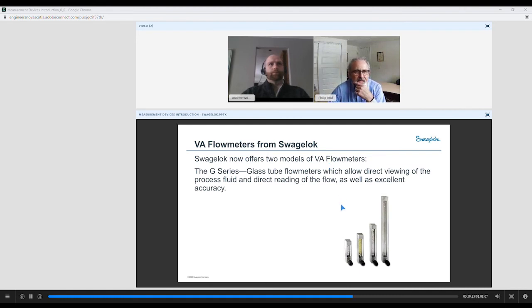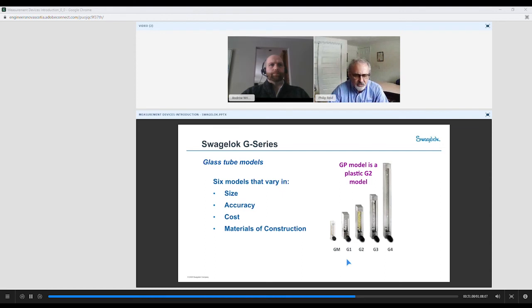So let's take a little look at these again. We offer sort of two models. We offer these in glass tube and some in plastic. There are some others, but they allow direct viewing, as we mentioned, from the front, and excellent accuracy ranges. The longer the tube, the higher the accuracy. The smaller the flow meter, the lower the accuracy. So again, very low, inexpensive setup costs here. On the glass tube models, there are 6. We also have a plastic model as well if you have very benign or non-aggressive media. So 6 models, and they vary in size and accuracy. Of course, as accuracy and size increase, cost will go up, and the materials of construction may change as well.